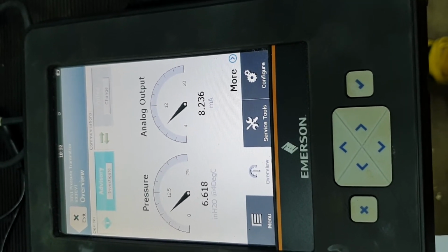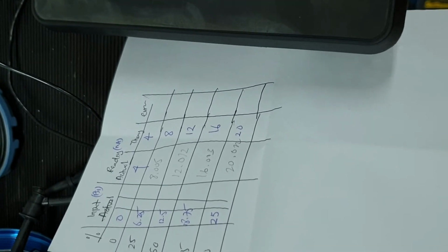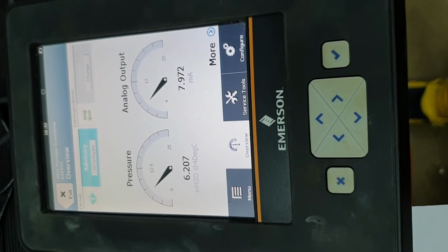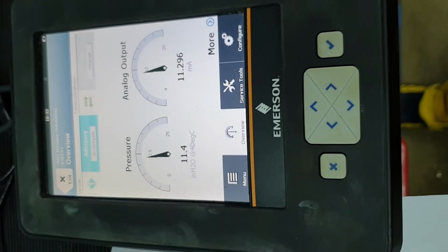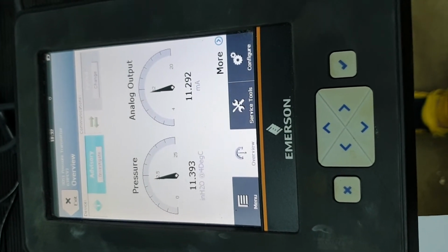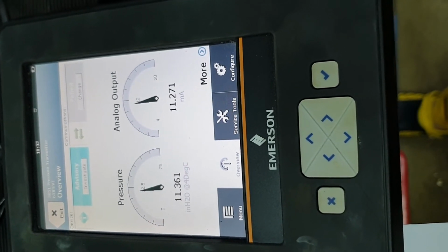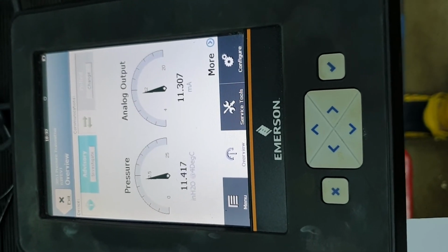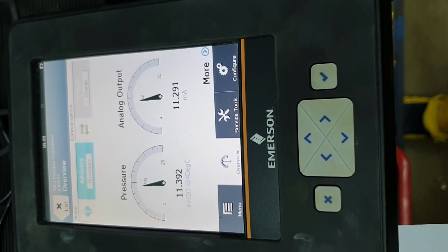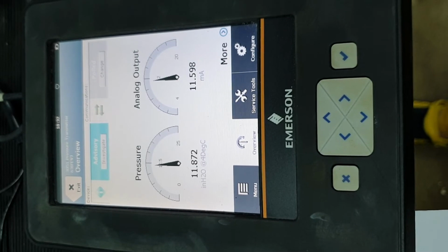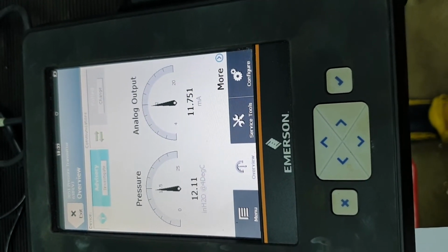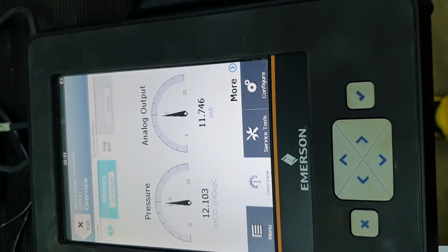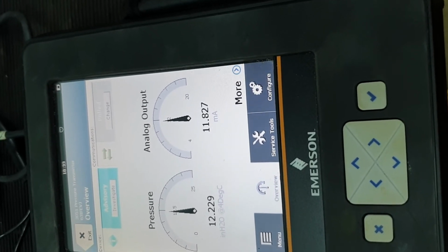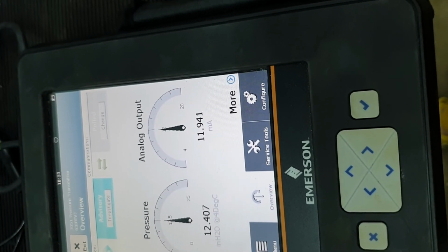Again, next we will increase further into the next step, which is 50%, about 12.5 inches H2O, and it is expected to be equivalent to 12 milliamp. As you can see, the reading here is not really accurate because of the sensitivity of the calibrator itself. However, we're going to reach the value as per the desired input as well as the current. So at 12.5 we'll be getting a current of 12 milliamp. Okay, we should be there, actually almost there, 12.5.